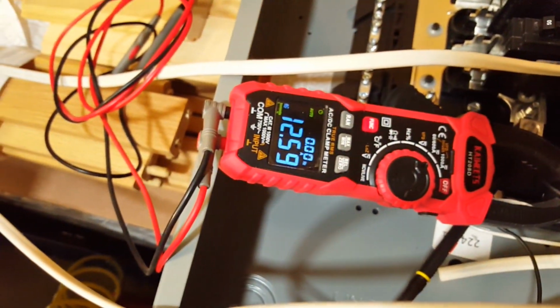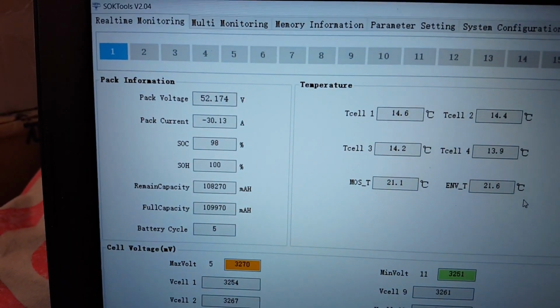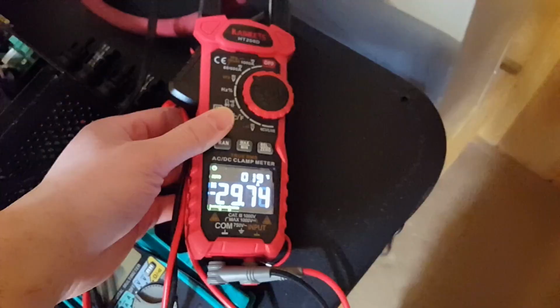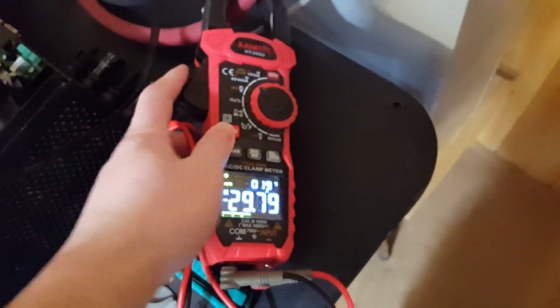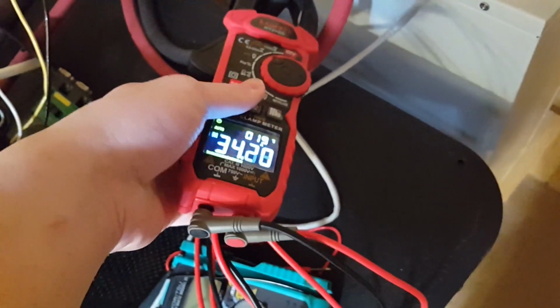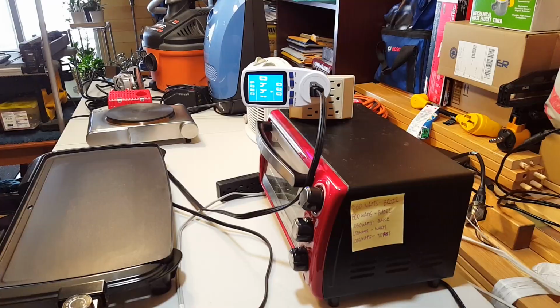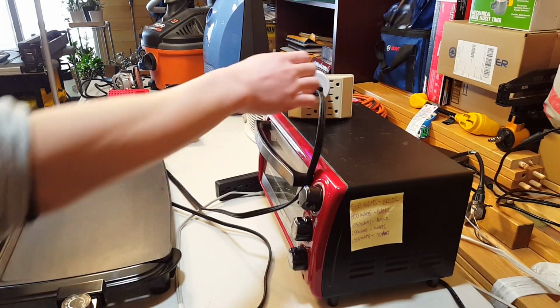AC amps is 12.5. BMS monitoring says 30 amps on the DC side. We'll check with our clamp meter. The load over here is still 1450 for the hot plate, so pretty much no difference. DC amps 29.7 on one cable, and then the other cable is doing 34. The next load we have, space heater.